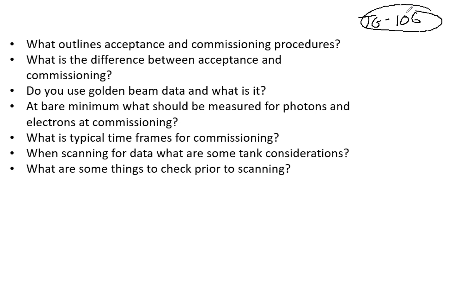Golden beam data is very important to understand. It is essentially a standardized data set that installers from Varian or Elekta attempt to match when they install a machine in your clinic. TG106 says you can use this, but use caution and take direct measurements to verify that the golden beam data is correct — because this data goes into your treatment planning system, and if it isn't exactly correct for your machine and setup, all your dose estimates will be incorrect.